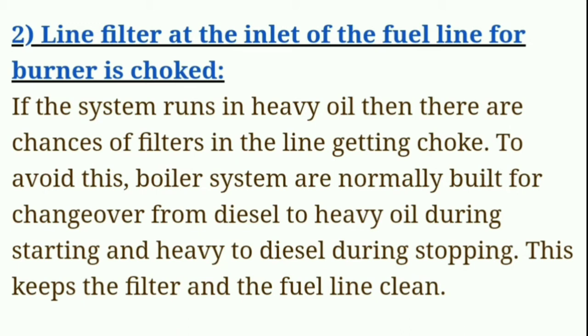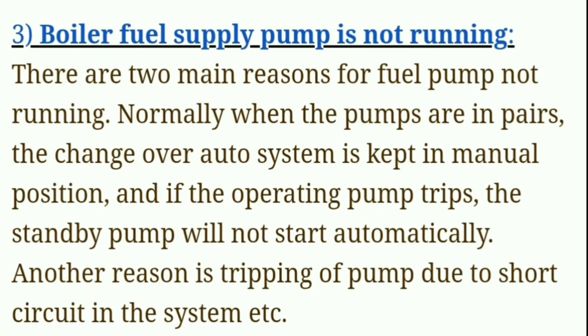Second, the line filter at the inlet of the fuel line for the burner is choked. If the system runs on heavy oil, there are chances of filters in the line getting choked. To avoid this, boiler systems are normally built for changeover from diesel to heavy oil during starting, and heavy oil to diesel during stopping. This keeps the filter and the fuel line clean.